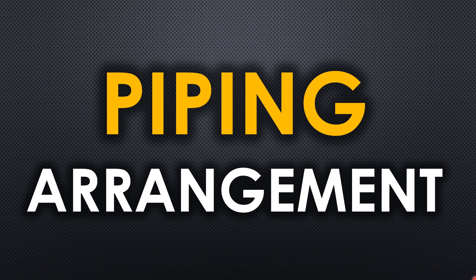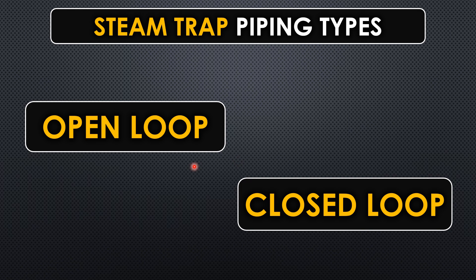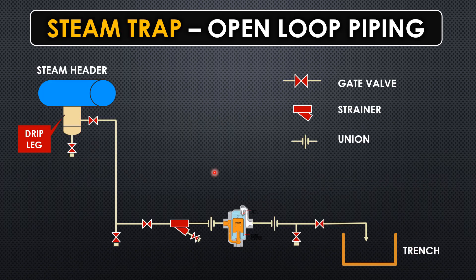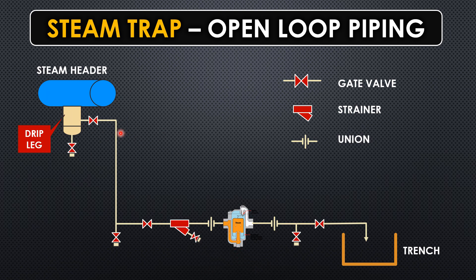Now let's see the piping arrangement of the steam trap. Generally there are two types: open loop and closed loop. In the open loop type, from the steam header you provide a drip leg with a drain. From the drip leg, a line drops down with an isolation valve, then another drain, followed by another isolation valve, a strainer, the steam trap, another drain, another isolation valve, and then it goes to the trench.